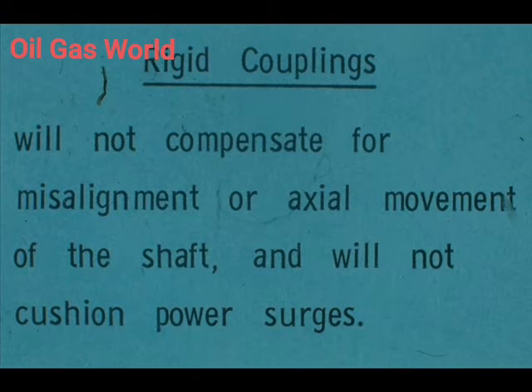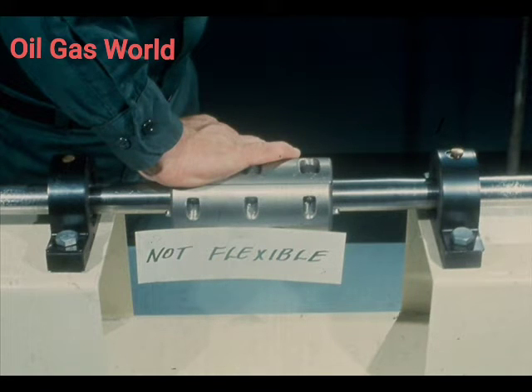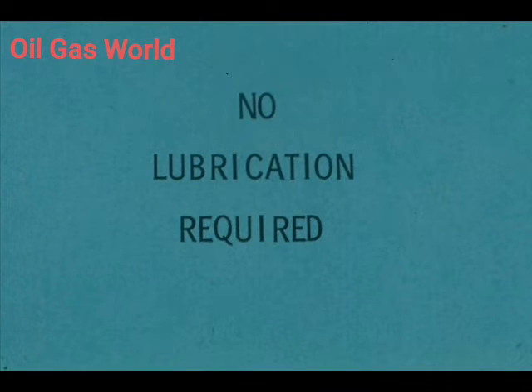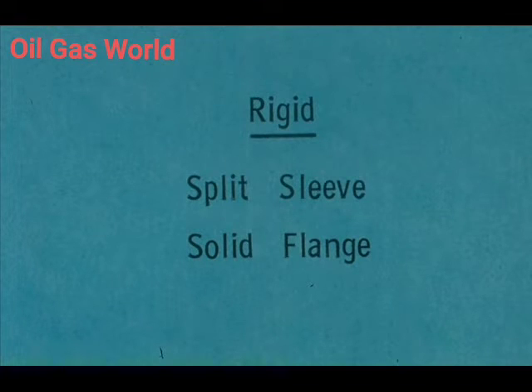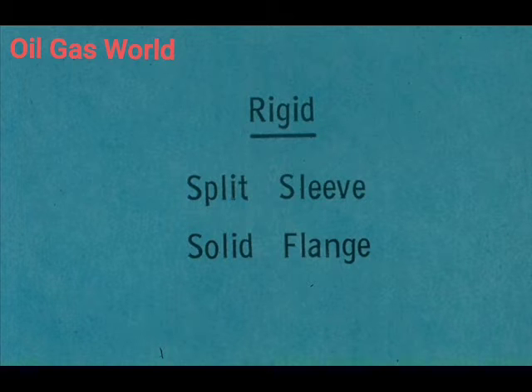Because of the solid connection of a rigid coupling, it does not offer very many advantages. It will not compensate for misalignment of the shafts or for axial movement of the shaft, and it will not cushion power surges. This is true of both the sleeve and the flange coupling because of their rigid construction — they are not flexible and will not absorb misalignment or any type of shock. The one advantage of the two rigid couplings is that neither of them require lubrication since there are no moving parts to create friction. The two types of rigid couplings are the split sleeve and the solid flange.